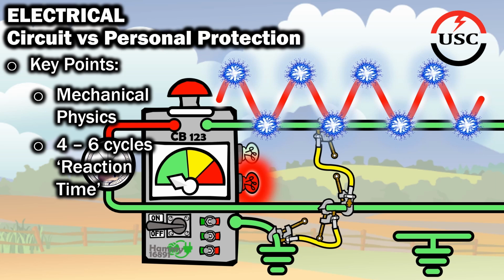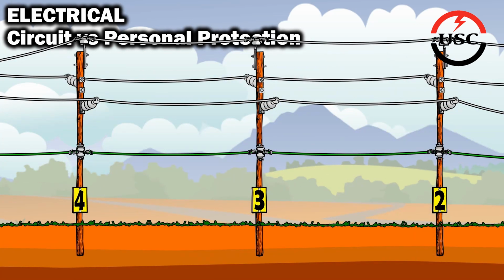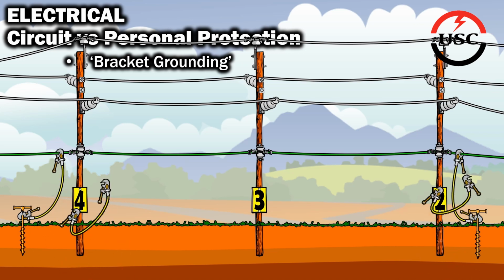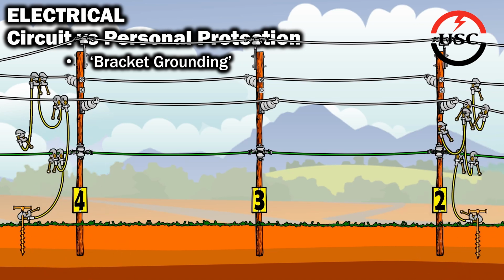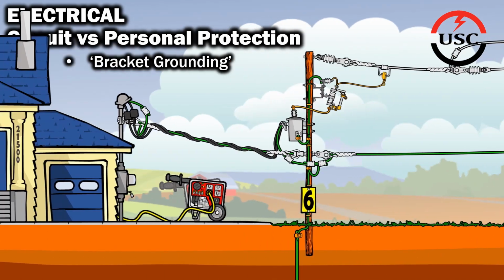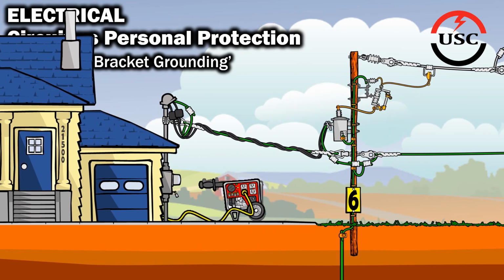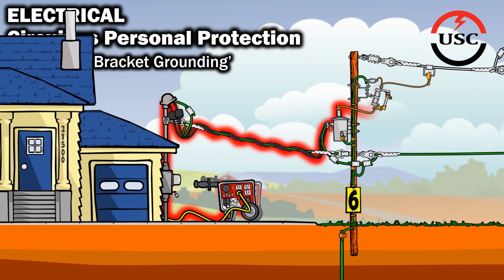Going back in time a bit. In the beginning, there was bracket grounding. It was considered the staple of personal protection. In actuality, it did little more than just provide a warm and fuzzy false sense of security for the worker. Bracket grounding is the practice of installing grounds on both sides of the work location.